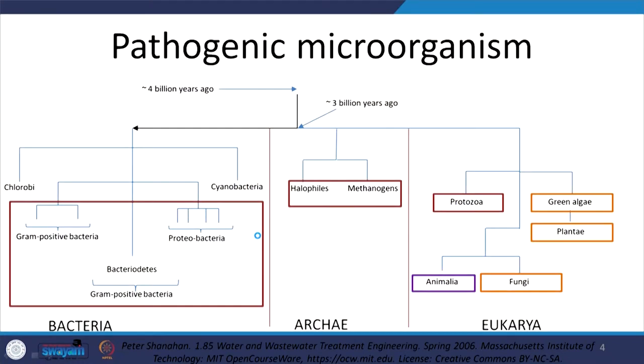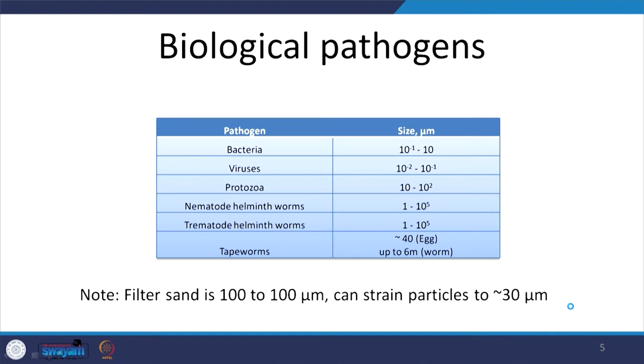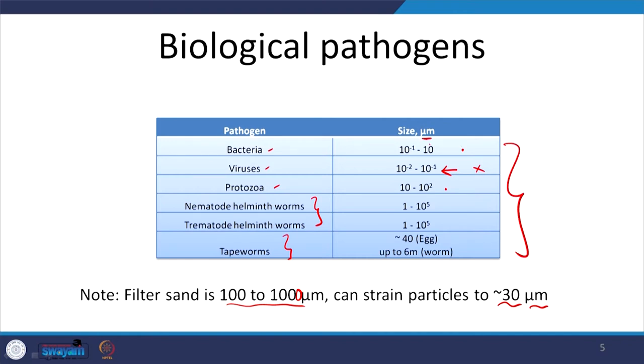We were talking about pathogenic microorganisms. The organisms we need to be concerned about include bacteria, archaea, and eukarya. In terms of sizes: bacteria, viruses — which are just RNA and therefore remarkably small — protozoa, and some kinds of worms. Filter sand is 100 to 1000 micrometers and can strain particles down to about 20–30 micrometers. So obviously we cannot remove viruses, but we can remove protozoa and sometimes some bacteria.